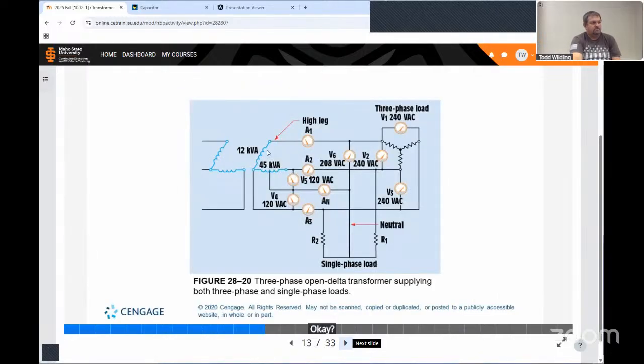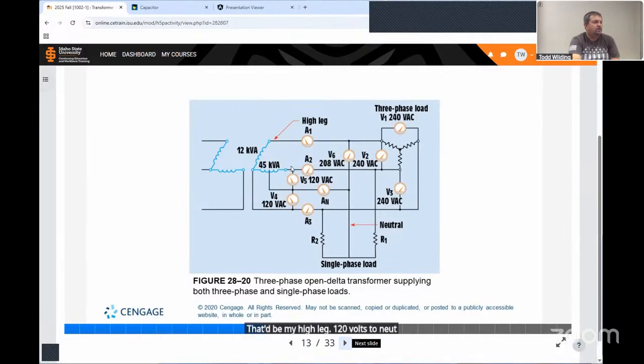Okay, so here's my open delta. I got a high leg. I think they're using that as my neutral. Tap is for a neutral. That'd be my high leg. 120 volts to neutral here. 120 volts to that one there. 208 phase to phase here. Phase to phase here would be, I believe it's 240. Maybe it's 208. I can't tell. Should be 240. No, that's going to that one. So on this, let's see, 20.